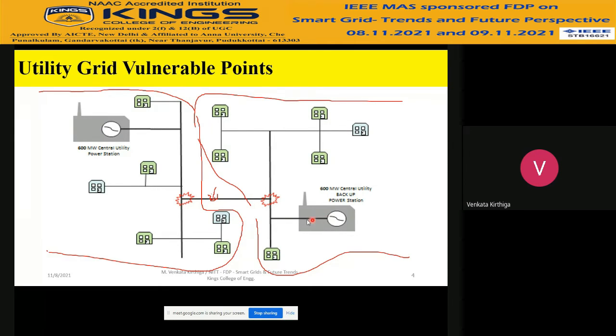And this power station will be feeding it because there is complete continuity here. So this will be giving up the current. Now this will also load this tie line, and there is a vulnerable point where the thermal stability of this line may be overcome, or it may cross its thermal stability. So what will happen is this tie line may lose its elasticity, and there is a chance for this line to get isolated when the current becomes overcurrent.